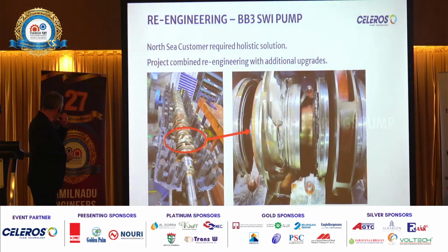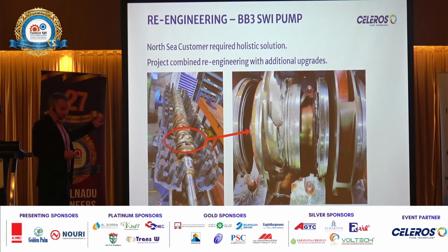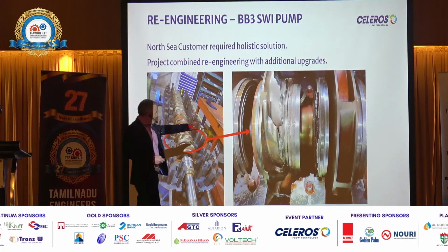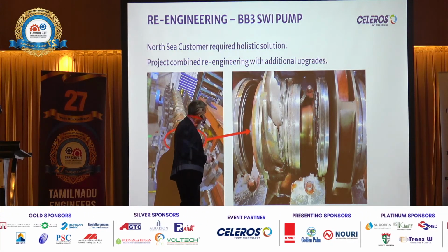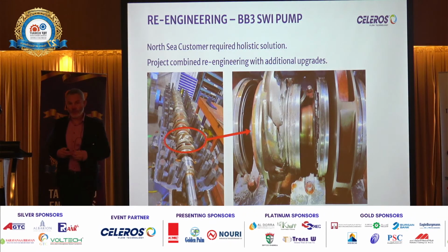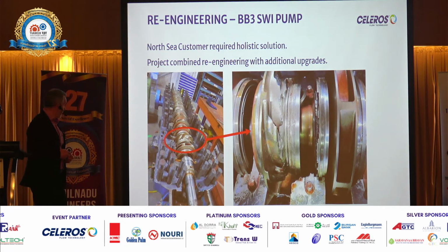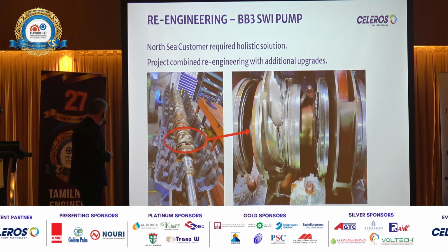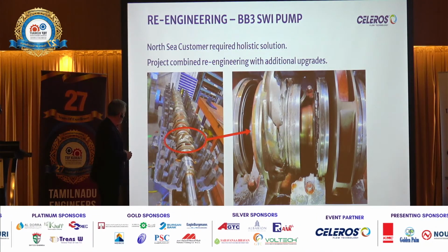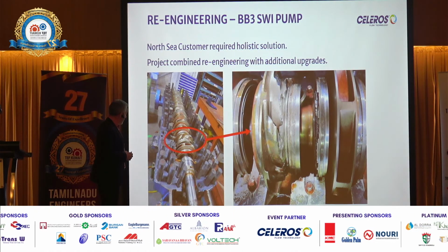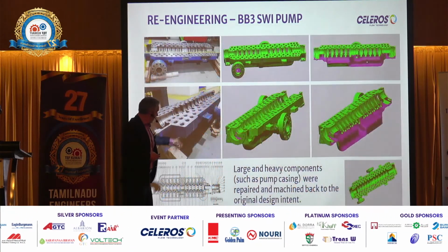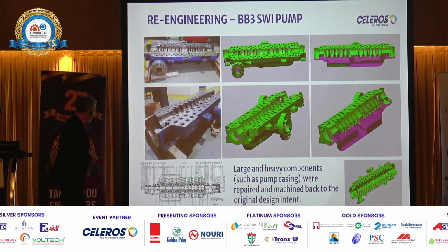And then this is a big BB3. This was quite a comprehensive project that we did, and you can see the impeller totally scrap. There's nothing on that. But because we're a pump OEM, we design and manufacture pumps, we design and manufacture BB3s, we were able to regenerate the model or the shape, the geometry of the impellers. Even if that was a one stage, we can regenerate, once we do the scanning, the actual impeller.